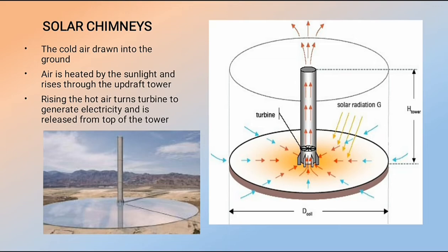The solar chimney has three main parts: collector, turbine, and chimney. The collector produces hot air using the greenhouse effect; it is usually made of glass or thin film and covers a large area five to six meters above the ground. Being a glazed collector, it converts about 70% of solar radiation into heat. The turbine, placed horizontally inside the chimney, is driven by the rising hot air to generate electricity and extract maximum energy.